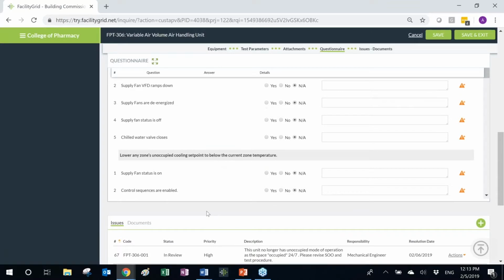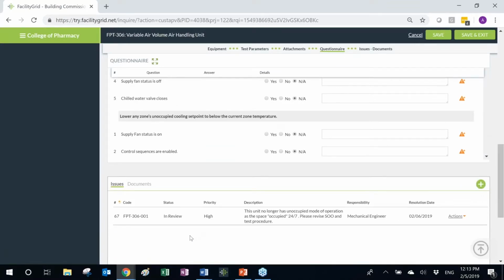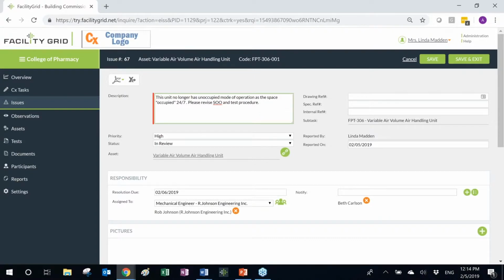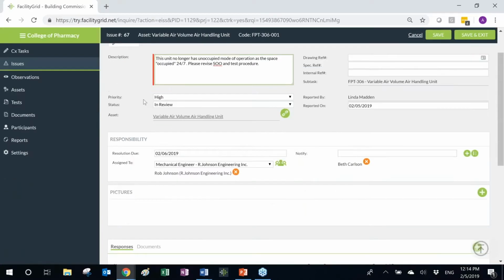So I've already done it, and basically I'm going to show you how the issue managing process would be handled in Facility Grid. So again, as a controls contractor, I went through the procedure. I realized that a certain procedure is not applicable to this specific test. So I documented this in the description section of the issue by stating that this equipment no longer has an unoccupied mode of operation, as the space is occupied 24/7. Now I'm asking the engineer of record to revise the sequence of operation, and also I'm asking the commissioning agent to update the test procedure. So I created an issue.